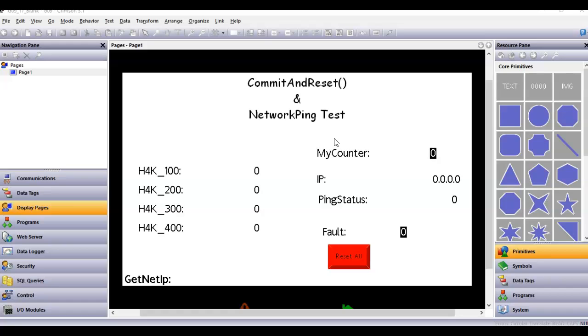They've got something going wrong with their PLC communications, and for some odd reason on their network, they find that if they cycle power to the HMI, everything comes up and starts working.